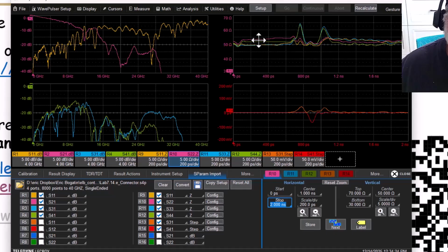And so what I see is here is some uniform traces. They're not all the same impedance in this example. Here's a launch of the connector for a couple of the pins. Here's the connector region. Here's the launch on the other side of the connector, and here's the daughter card on the other side of the connector. And so I can read the impedance right off the front screen here. They're within about plus or minus 2 ohms, 1.5 ohms of each other.